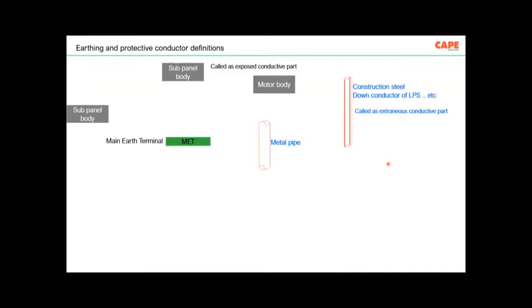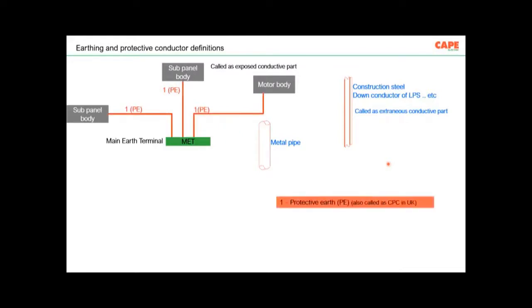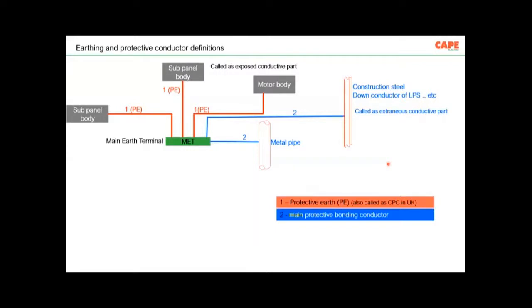You have to have an equipotential bonding bar, which is called MET, or a bus bar, which is offering a potential very close to the earth potential, zero potential, which is going to be the reference of this entire building. Now, all the exposed conductive parts are connected to MET through, I have given a red color, actual color is green and yellow, but just for identification, I gave red color. These are called protective earthing conductors. The extraneous conductive parts, such as metal pipe and other metal parts, are connected to the MET through the blue color wire, which is called a protective bonding conductor. That means at the mains incoming, MET is very close to your mains incoming panel, the main switchboard, and at the main switchboard, you are supposed to make protective equipotential bonding.